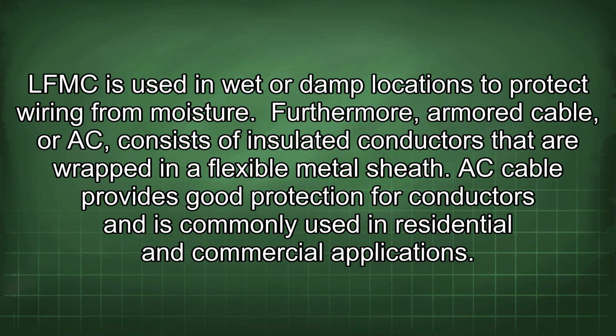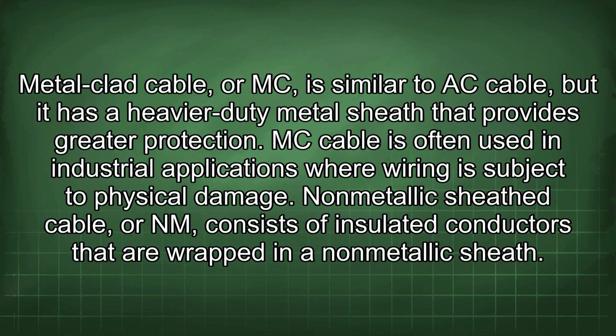Furthermore, armored cable, or AC, consists of insulated conductors that are wrapped in a flexible metal sheath. AC cable provides good protection for conductors and is commonly used in residential and commercial applications. Metal-clad cable, or MC, is similar to AC cable, but it has a heavier-duty metal sheath that provides greater protection. MC cable is often used in industrial applications where wiring is subject to physical damage.